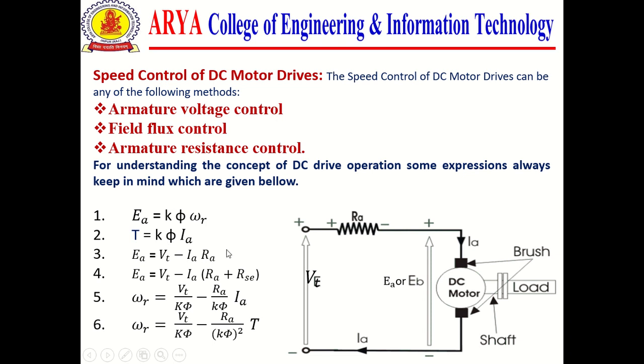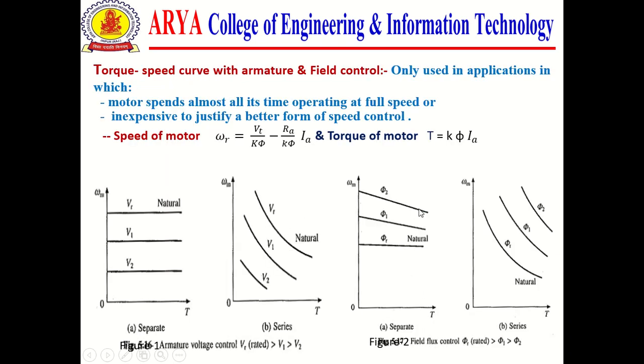So this is the impact on this characteristic. So these are the impacts of armature voltage or field weakening. If we decrease the flux, then we increase the speed without changing the value of torque. So this method is used above the base rated speed of the drives.